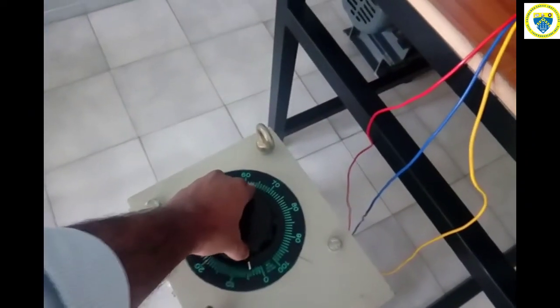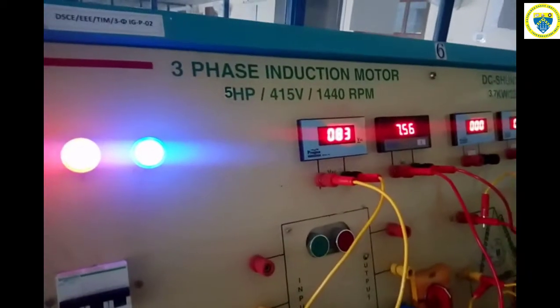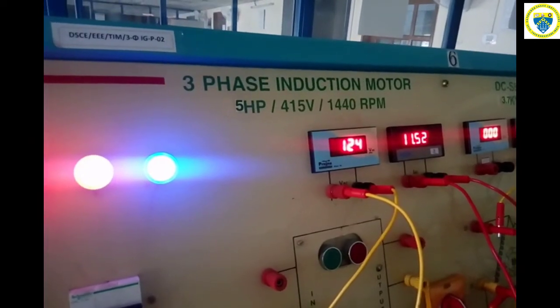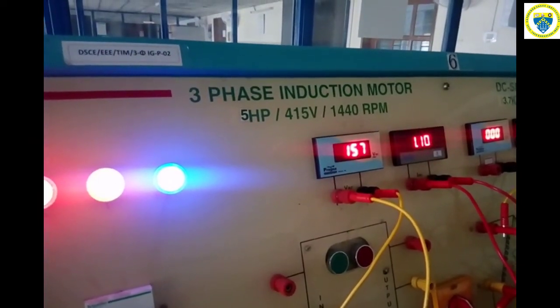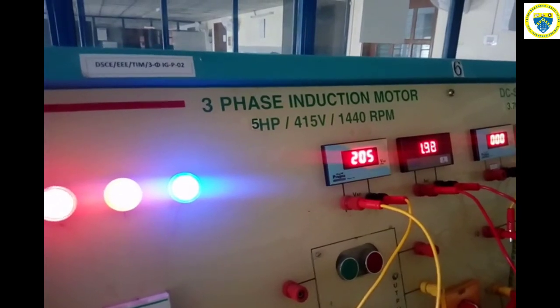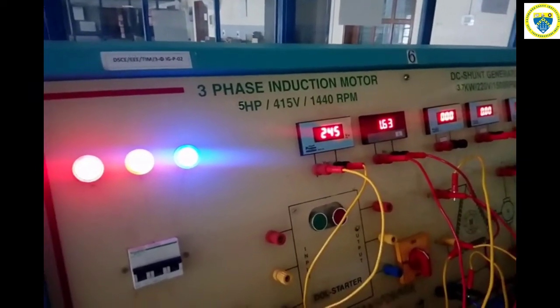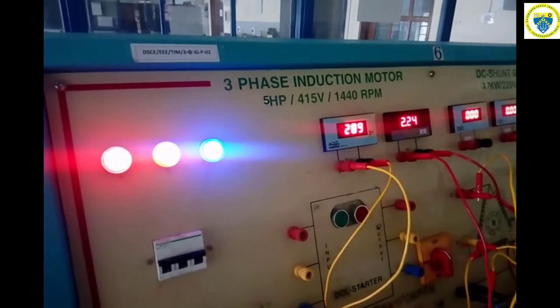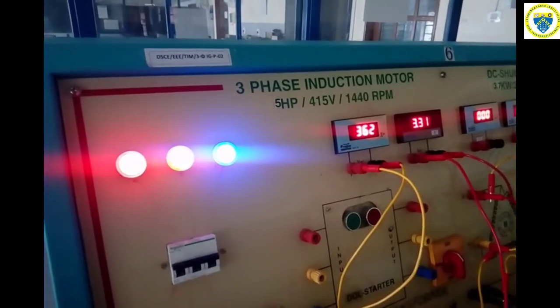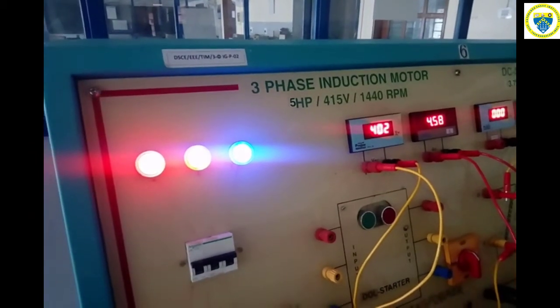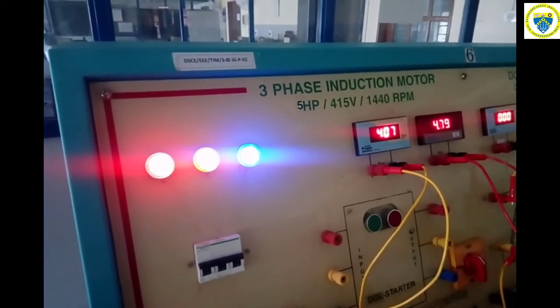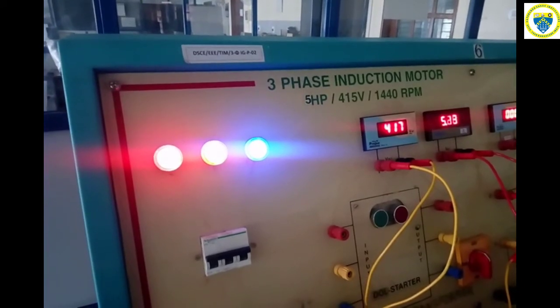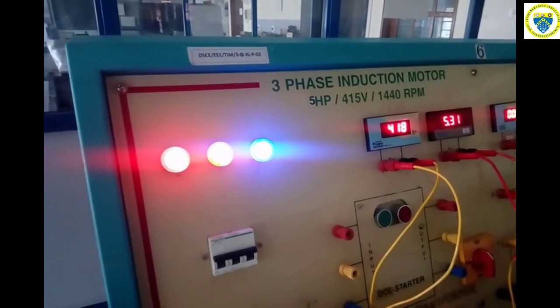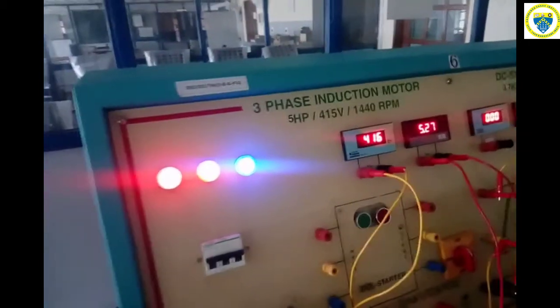Now gradually vary the auto transformer from 0 to the rated voltage of 415 volt. The motor starts rotating. Slowly vary the auto transformer and see that it is running at the rated voltage of 415 volt. So it is 400. Now slowly increase the auto transformer and make that voltage 415 volt.